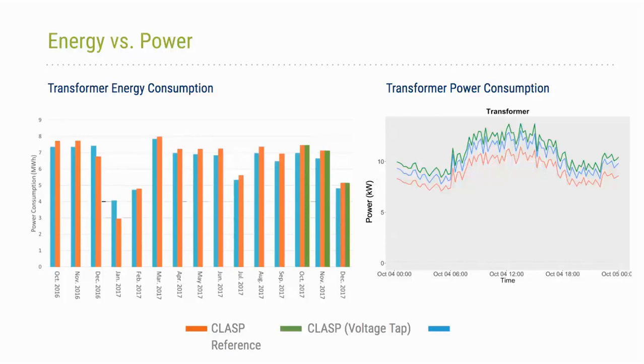But here I just want to show you on the left side, for example, the energy consumption of the transformer. If you take a look at January, the error is actually much higher. There's a much bigger discrepancy between the reference and the CLASP system. And we expected this because the wireless CT was, I guess, measuring small amounts of current in this case. So they were only recording small amounts of current, and that is definitely detrimental for the accuracy of the sensor. So if the wireless CT were to measure a much larger load, I think the performance of the system might improve. But if it's measuring very low currents, the accuracy of the system diminishes considerably. Next slide, please.